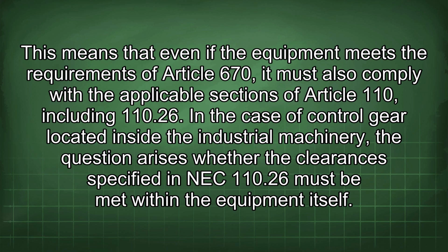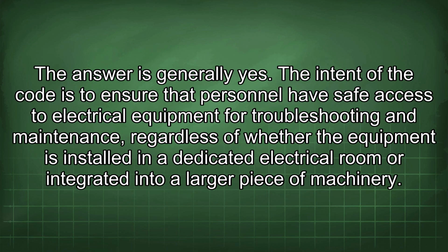In the case of control gear located inside the industrial machinery, the question arises whether the clearances specified in NEC 110.26 must be met within the equipment itself. The answer is generally yes. The intent of the code is to ensure that personnel have safe access to electrical equipment for troubleshooting and maintenance, regardless of whether the equipment is installed in a dedicated electrical room or integrated into a larger piece of machinery.